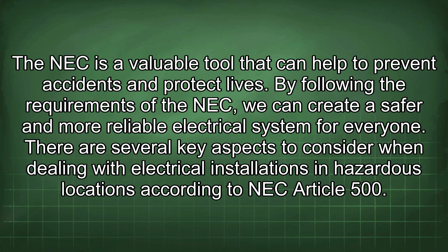There are several key aspects to consider when dealing with electrical installations in hazardous locations according to NEC Article 500. Firstly, understanding the classification of the location is crucial. This involves determining whether the location is Class I, II, or III, and then further classifying it as Division 1 or Division 2, based on the likelihood of the presence of hazardous materials. Secondly, selecting the appropriate equipment is essential. Equipment used in hazardous locations must be specifically designed and certified for the class, division, and group of the location. This equipment is designed to prevent ignition of the hazardous atmosphere.